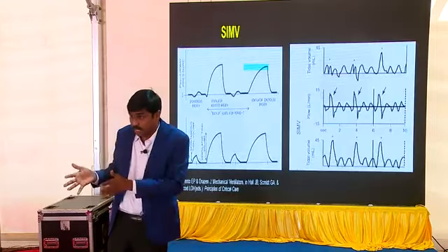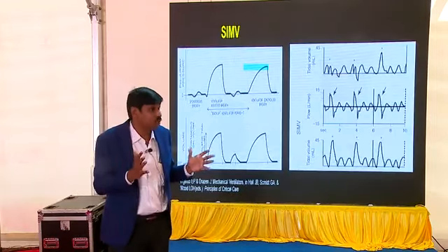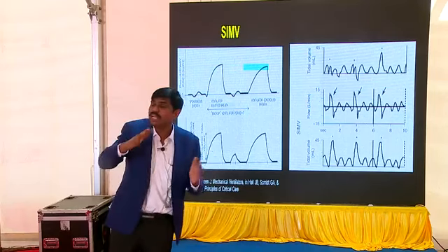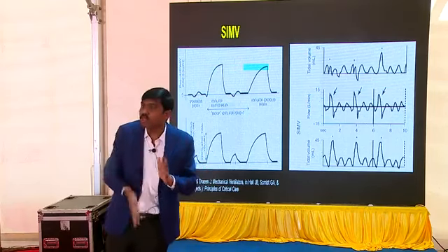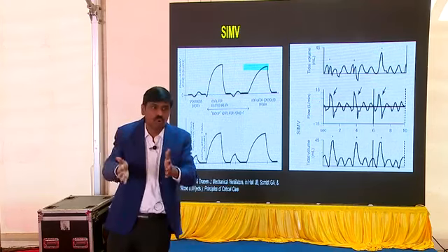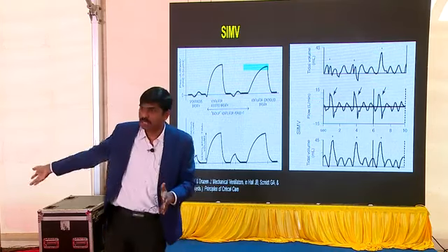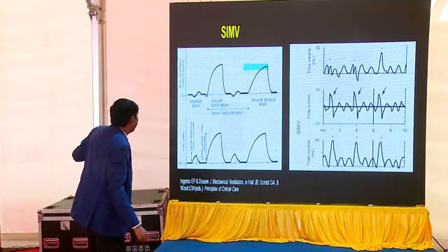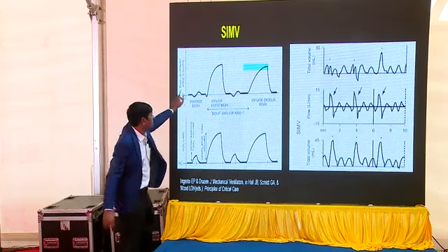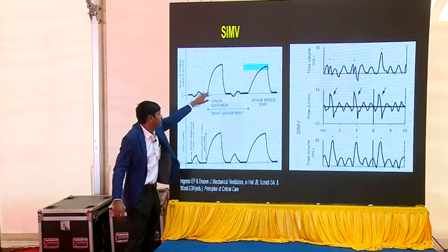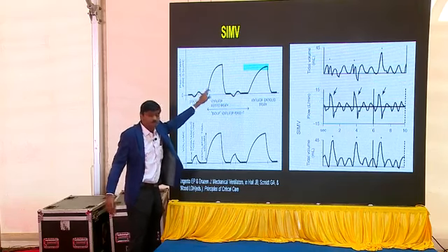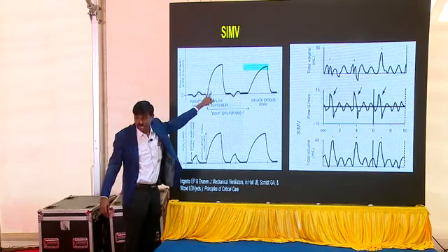Now, out of that window period, it won't synchronize, but at least it waits for the baby to tell, okay, it's going to start breathing. If it starts breathing, immediately it catches on to that, and then expiration will be based upon the time only. Once the time is over, 0.3 seconds over, it moves to expiration. So you find here, now if you see here, this is a baby-initiated breath.